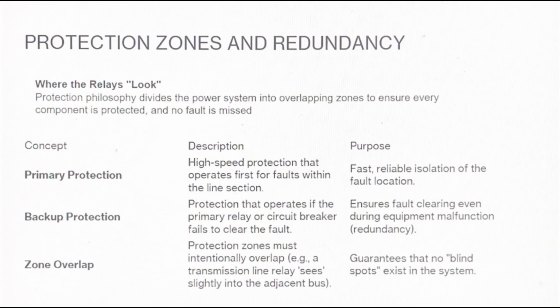But what happens if the primary relay fails? Or, more commonly, the circuit breaker it commands fails to open. That's where backup protection comes in. Every single component must be covered by a secondary, slower protection scheme that will operate if the primary system fails. This redundancy is non-negotiable. The zone overlap is the mechanism that ensures everything is covered. By having each relay see slightly past its own equipment into the adjacent bus or line, we guarantee there are no unprotected blind spots in the system.